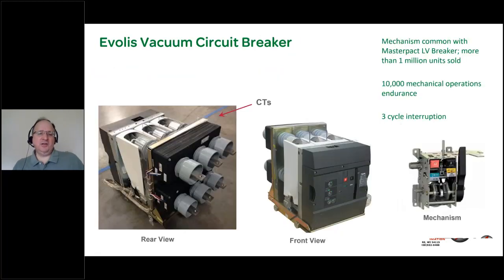This is a picture of the Schneider Electric Evolis circuit breaker, both a rear view and a front view of that breaker. It's one of the most popular medium voltage breakers in the world, with over 1 million units sold. It's rated for 10,000 mechanical operations, 3-cycle interruption. And again, from a width point of view, this is able to be installed in switchgear up through 15 kV, which is only 26 inches wide. And moreover, we're going to go to the next slide here.